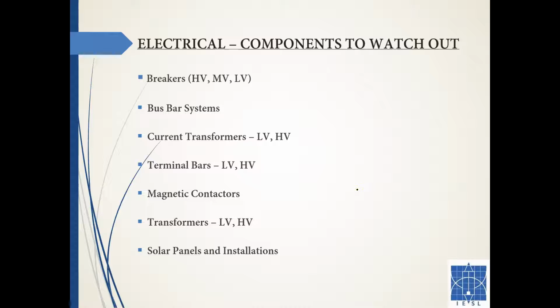What I suggest is to have what we call the bus bar sleeve, the matte finished bus bar sleeves, at least on the bus bar joints, so that someday when the thermographer arrives, he can get a better idea of your bus bar system. Same with all other components when it comes to bare metals. Bare metals are really low in emissivity. You need to make sure that your thermographer gets a proper idea, or your survey will be in vain.